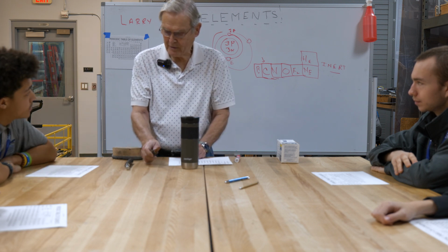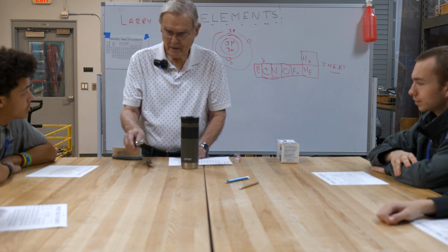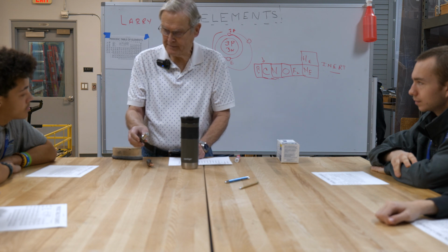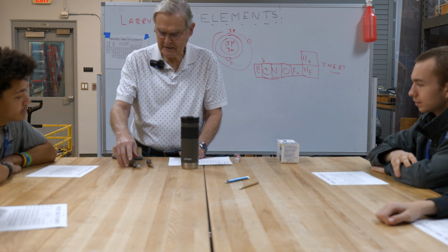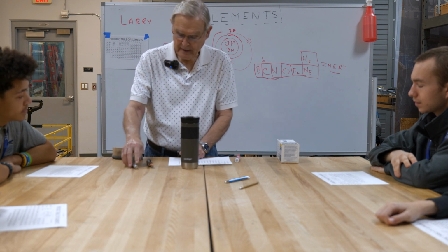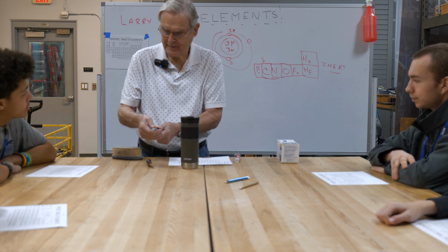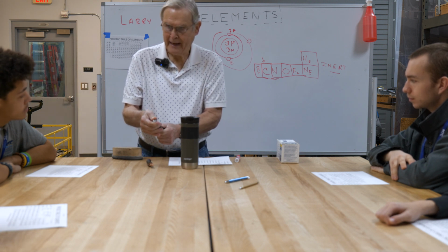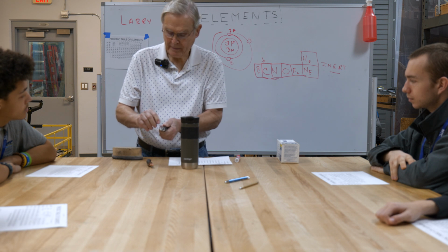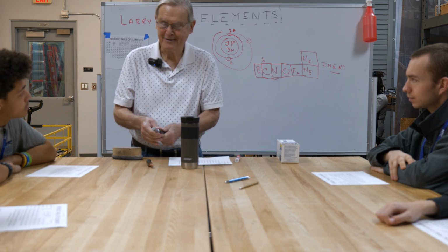This tends to be very malleable, as I said. This would be better, except you do experience some corrosion with aluminum. Not nearly as bad with copper. So you can set up aluminum oxides. The other thing that happens is when you squeeze down on this to terminate a lug, you tend to squeeze quite hard, and it has a tendency to flow. In other words, you've compressed it so tight that it flows out away from the junction and becomes a loose junction. Loose, not so good, because it'll catch fire.